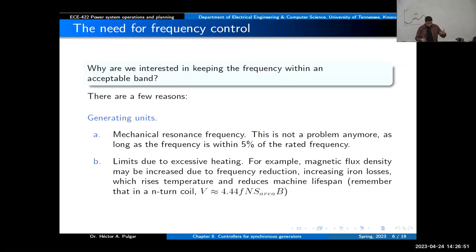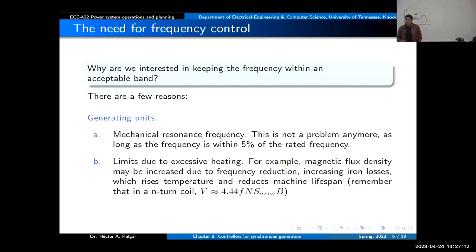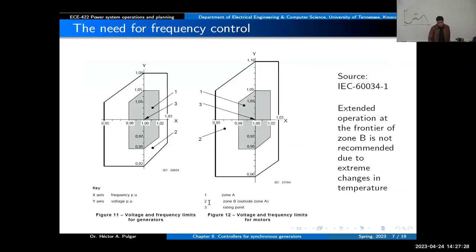The flux increases. And if the flux increases, you might have more losses and heat. Your components — transformer, machine — will heat up, and you will have losses. Here you have a norm that defines the typical range of operation for a generator and a motor. The x-axis is frequency, and the y-axis is voltage. There are different regions of operation: Zone A and Zone B. Certainly the inner region is a safer operating region — if you're in that area, you should be fine in terms of heating. If you move out of that area, it can be more dangerous and can lead to problems.